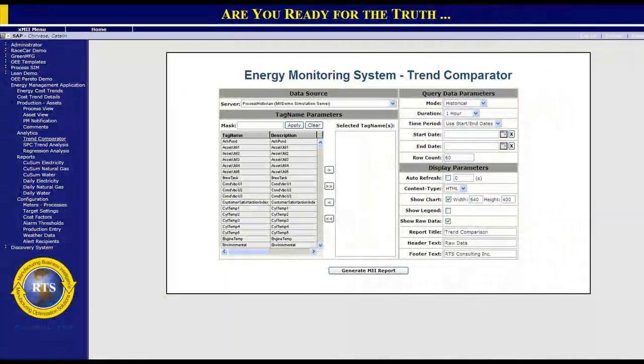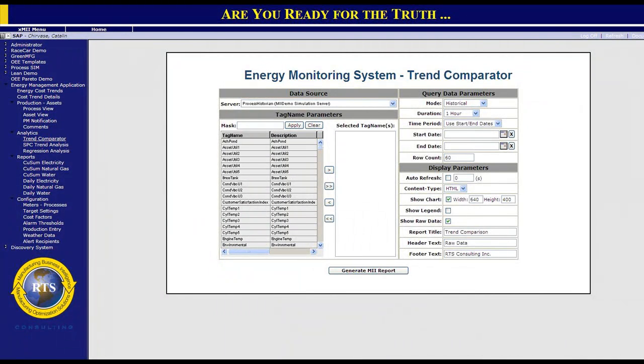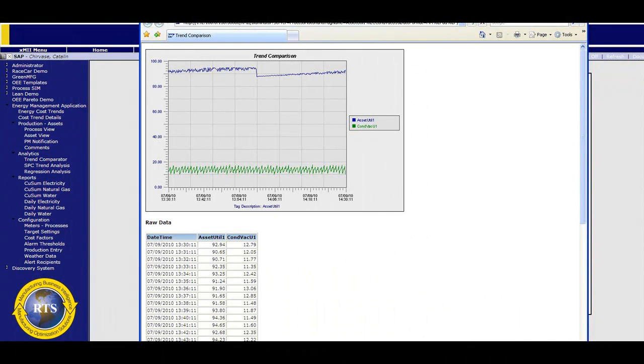The next screen shows detailed granular multivariable data and enables analysis on that data — such as energy to energy, or energy to process parameters. Energy to energy is very useful for looking at the efficiencies of a boiler or a compressor, whereby we can look at natural gas to steam conversion or electricity to compressed air. We select the data source, specific variables, and time periods, and generate a graphical and tabular result from the real-time query — exportable to Excel, of course.